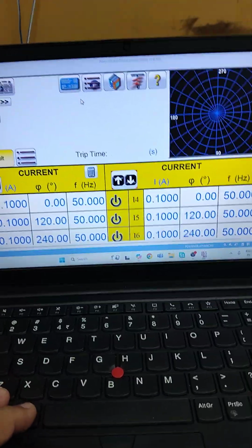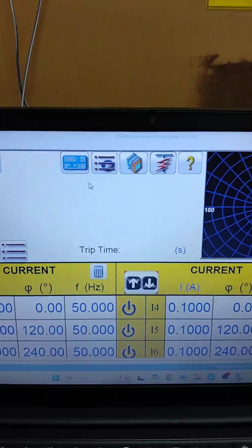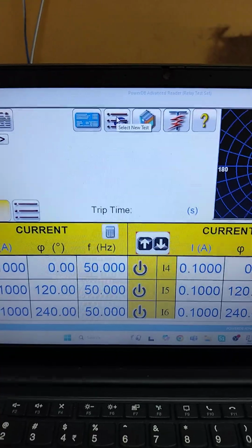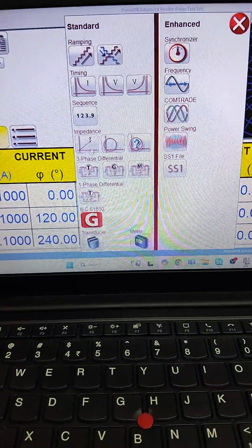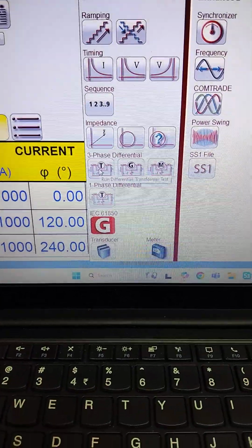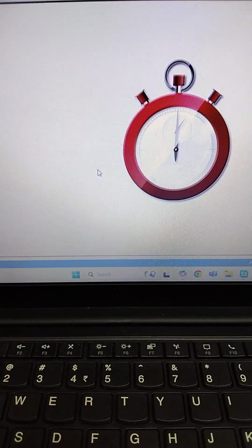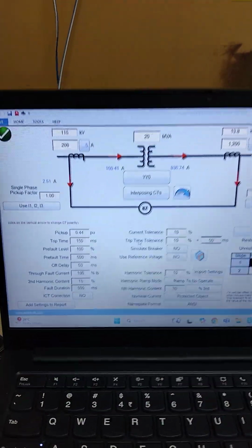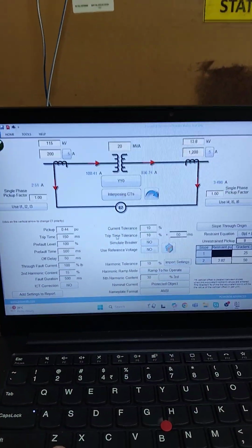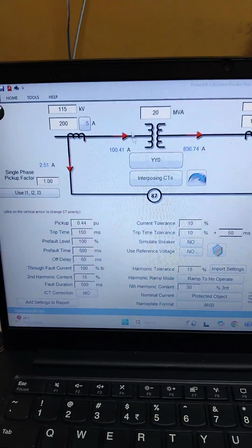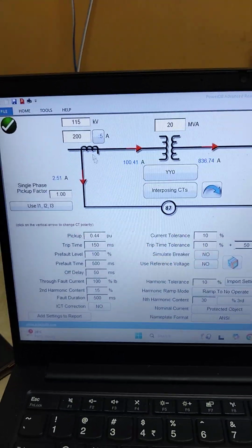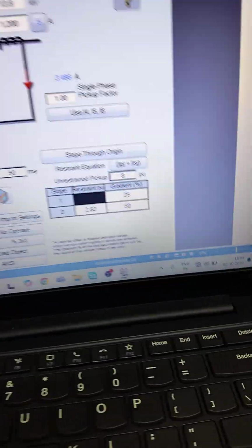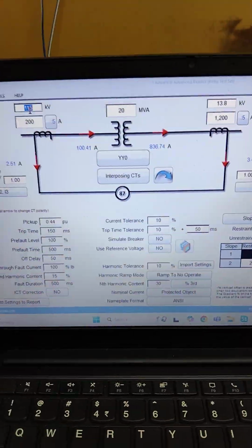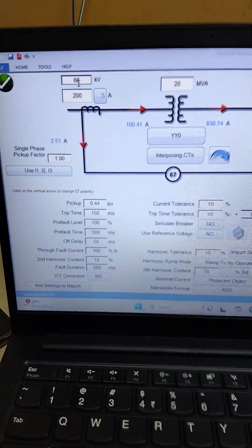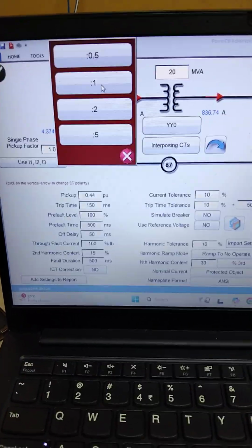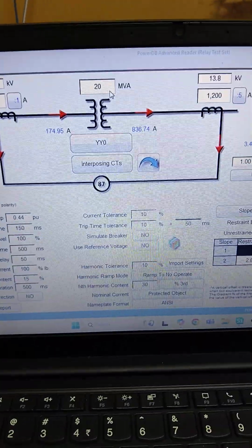Now we have to test the differential protection. So go into this new test tab. In that, in the 3-phase differential, we have a template ready. So just select it, and you can see that the transformer representation is coming with all the CT, VT, differential settings detail. So enter here 115 kV on the HV side, and CT ratio is 200/5 and MVA is 20.